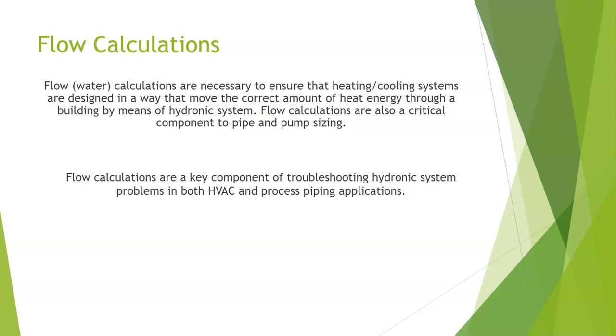As a design engineer, this is incredibly important as well because you need this calculation to size your pipes and pumps. You need to make sure that the system you're designing, let's say for a boiler, has enough flow going through it so that you get the proper delta T or temperature difference through that boiler so it condenses. Regardless of what piece of the pie you have in industry, you need to know this calculation.